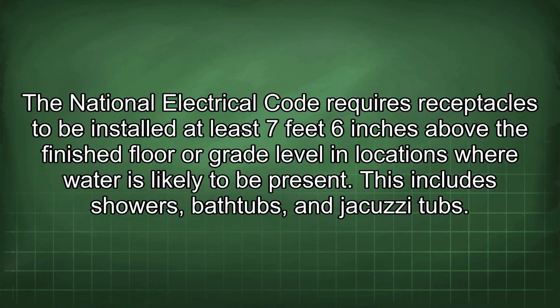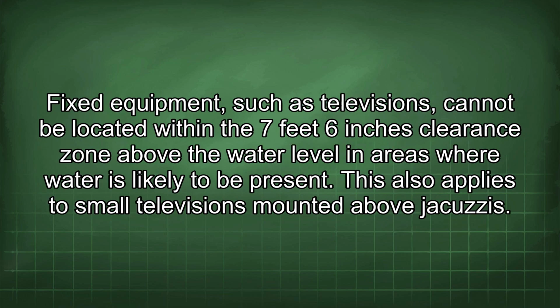The National Electrical Code requires receptacles to be installed at least 7 feet 6 inches above the finished floor or grade level in locations where water is likely to be present. This includes showers, bathtubs, and jacuzzi tubs. Fixed equipment, such as televisions, cannot be located within the 7 feet 6 inches clearance zone above the water level in areas where water is likely to be present. This also applies to small televisions mounted above jacuzzis.